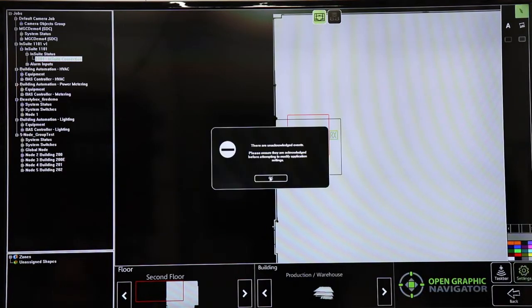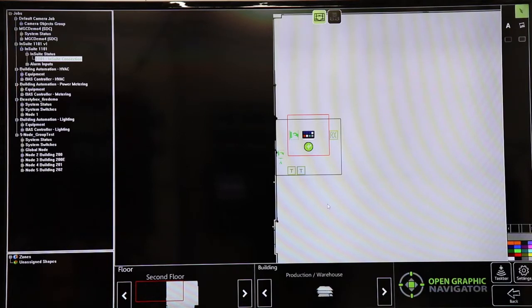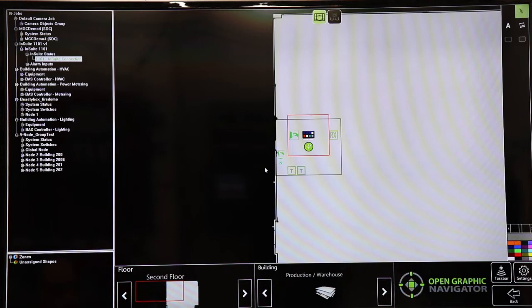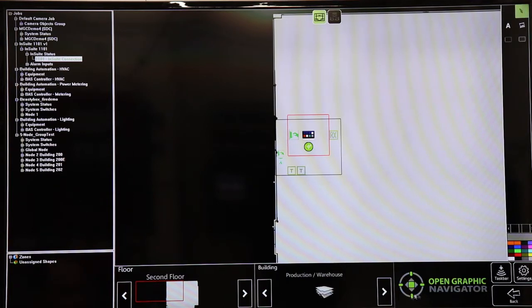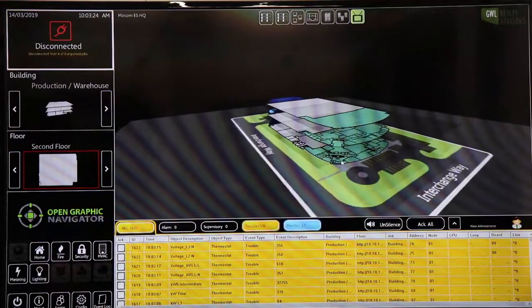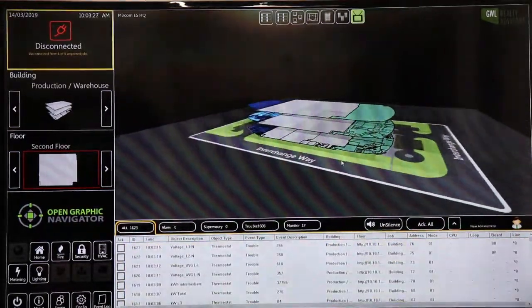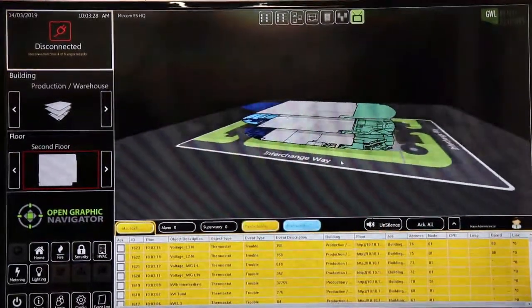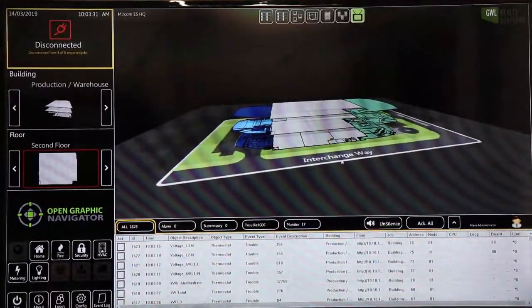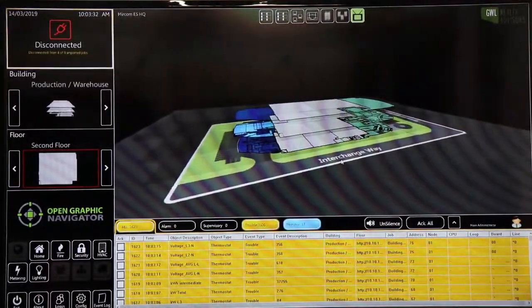Beyond placing the specific devices, I have this handy settings tool which will allow us to configure the behavior of the device in its different states. So for example, what do I want to present to the user in an alarm condition, in a trouble condition, an off normal condition, and a normal condition. You can see that we have also a little color palette here which supports creating 2D and 3D zones which can illuminate based on these different state changes. So overall, what we're presenting here is that all of the configuration is done within the OpenGN itself. It's a very handy built-in tool to move your devices around throughout the facility, to place them in their appropriate locations, and to configure the correlations and rules based on the state changes of the devices.